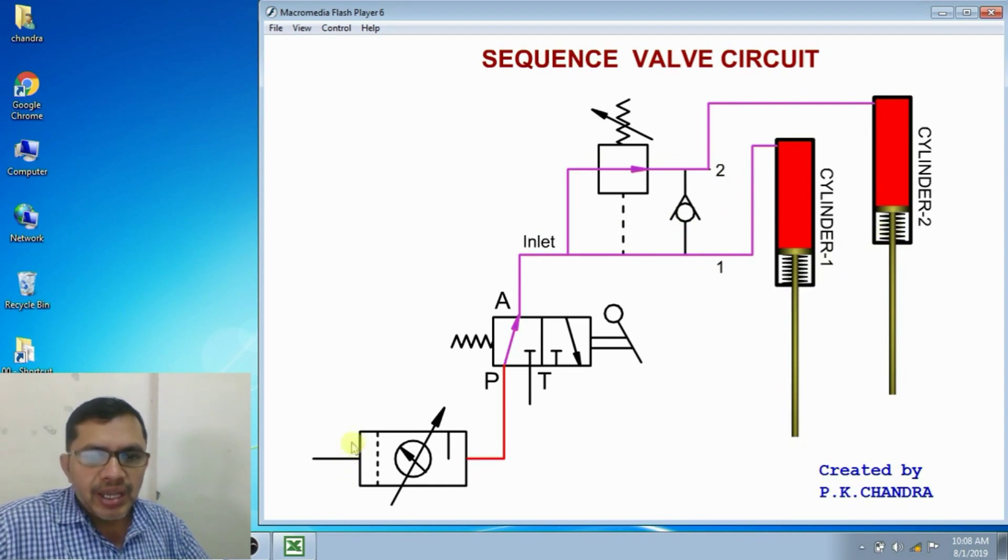And this is FRL unit, filter, regulator, lubricator. And this is 3x2 direction control valve. It has three ports, P, A and T. And it has two positions. In first position, P to A connection is there. T is closed. In the other position, A to T connection is there. P is closed.